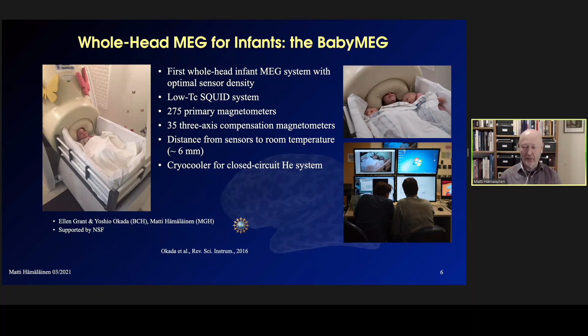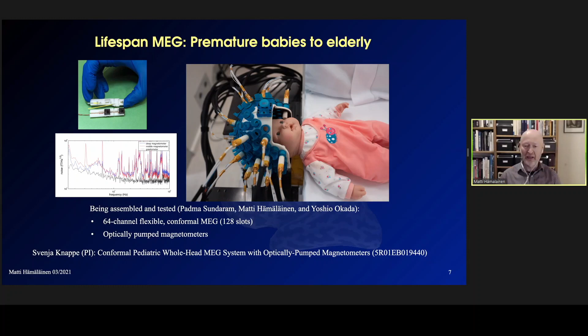The second device we have built is what we call a conformal MEG system. This device uses optically pumped magnetometers to record MEG signals around the head. And since the sensors are a little bit like big EEG electrodes, they can be positioned at will around the head, and they accommodate different head sizes. And here is the practical device being assembled in our laboratory, and on the right we have the acquisition electronics and electronics software, which has to be then connected to higher level software which we are building to actually acquire and store data from this device.